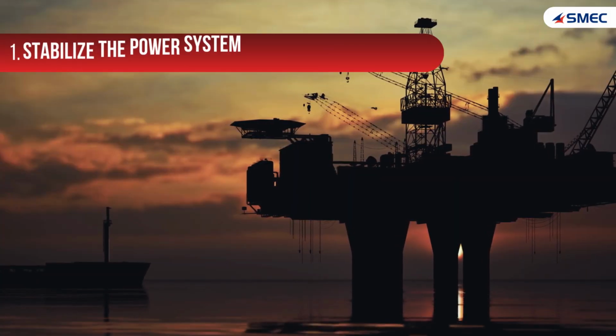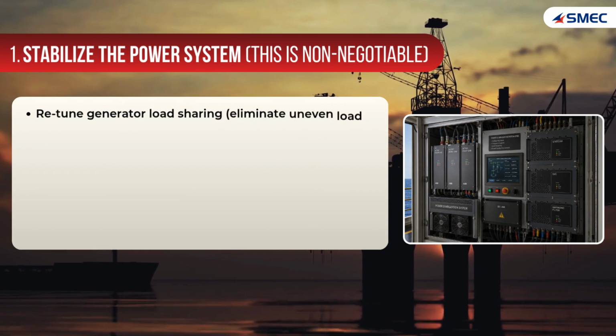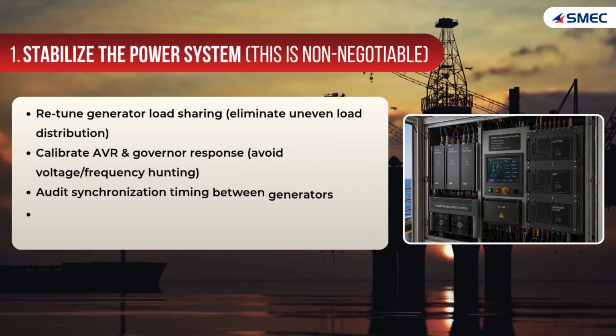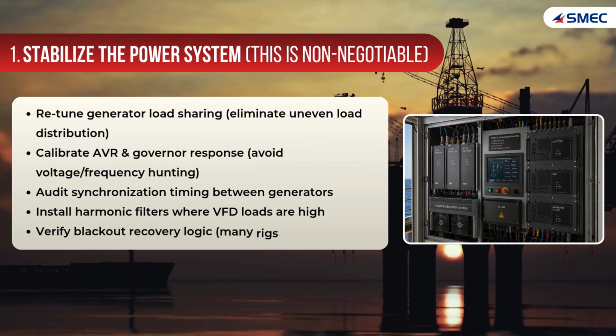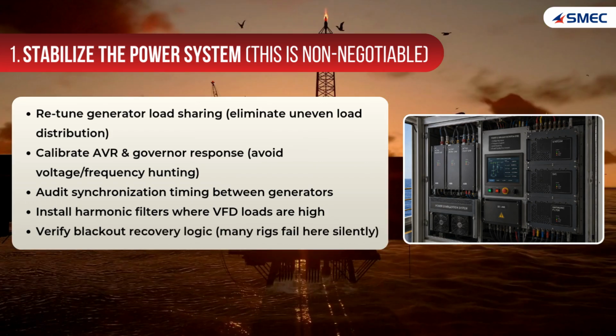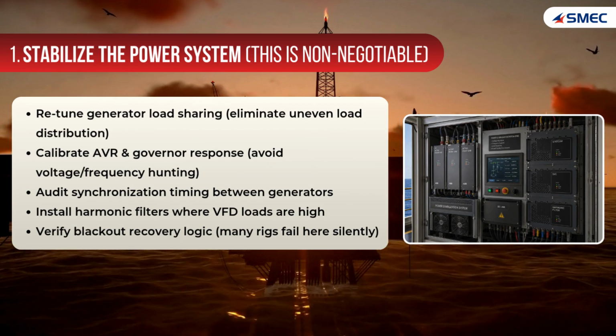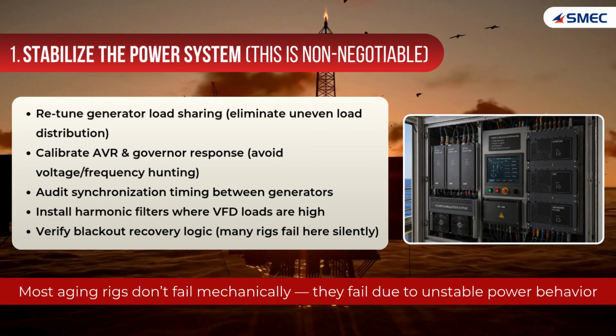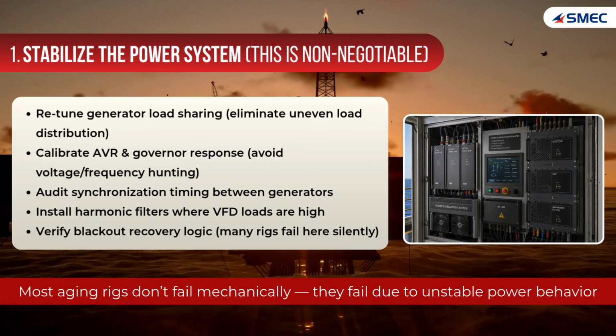First, stabilize the power. If your generators are hunting or load sharing is uneven, your electronics are dying. You must retune governors, audit synchronization, and install harmonic filters for your VFD loads. Remember, most aging rigs fail electrically before they fail mechanically.